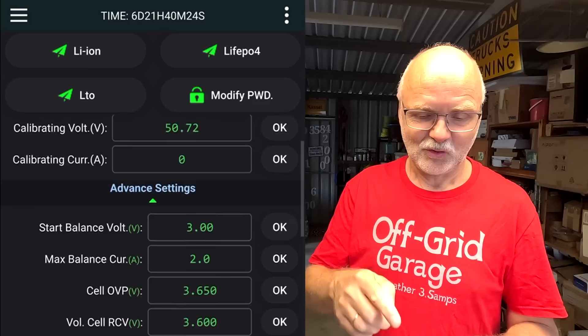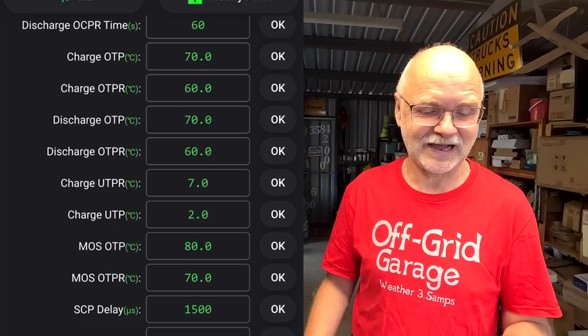And one of the complaints was that the charge under temperature is still sitting on -20 degrees. Yeah. So, and they have changed it now. Finally, they have changed it. The charge under temperature protection sits now on positive 2 degrees Celsius, and the recovery on 7 degrees Celsius. And this is the same for lithium ion. If you select the lithium ion profile or even the LTO profile, they're all sitting on positive temperatures now, not on the silly -20 anymore. So finally this is fixed, yeah. This was one of our complaints for a very long time. Finally they have done it.